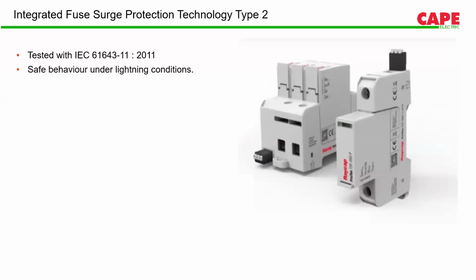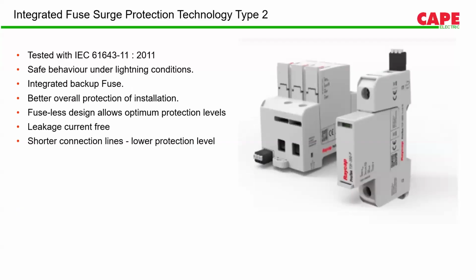Similar to type 1, we also have type 2 SPDs with integrated backup fuse. They also have a short circuit rating of 100 kiloamperes, especially for places in the DBs where there is a crunch of space. We can use this kind of SPDs, called the Protect T2F series SPDs.